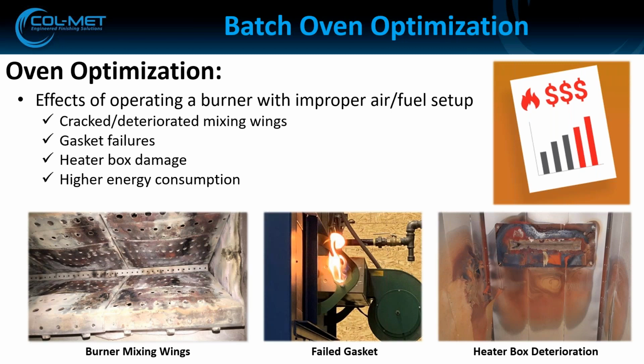So what you'd want to see is about 1 inch water column across the burner for air, and then between 5 and 8 inches water column for the fuel pressure, at high fire. And we have some detailed instructions on how to connect that and adjust the pressures if you need to.